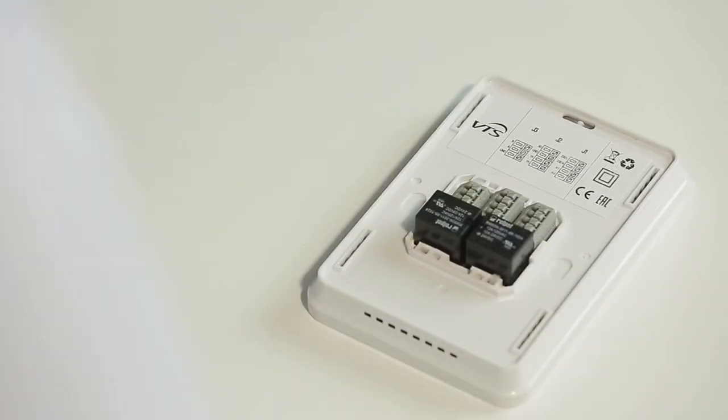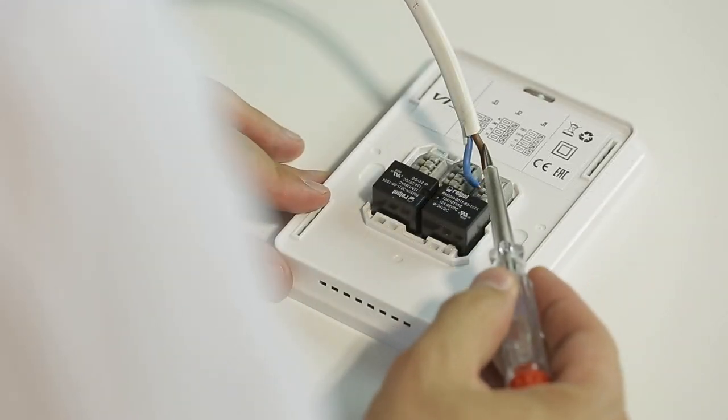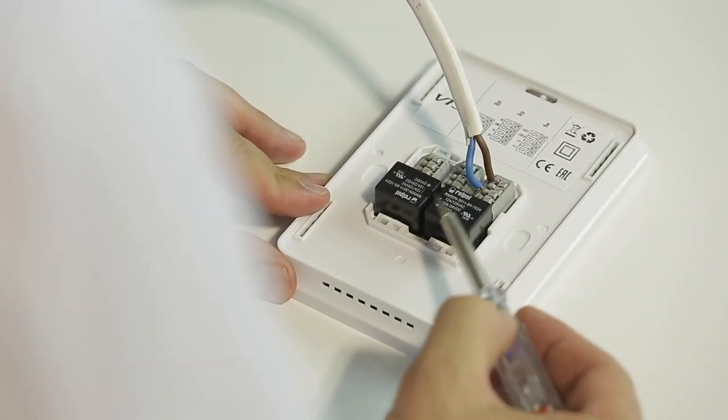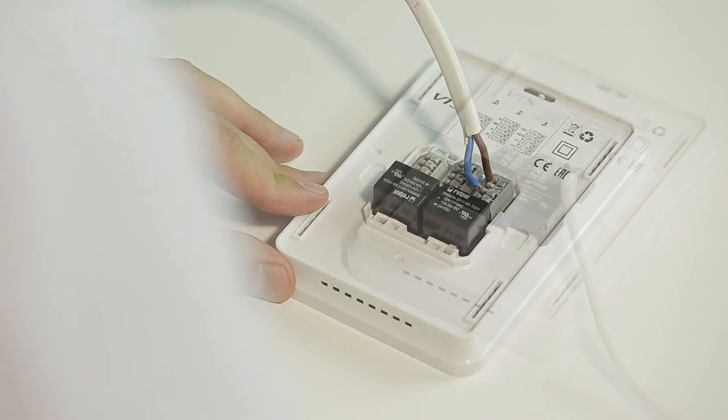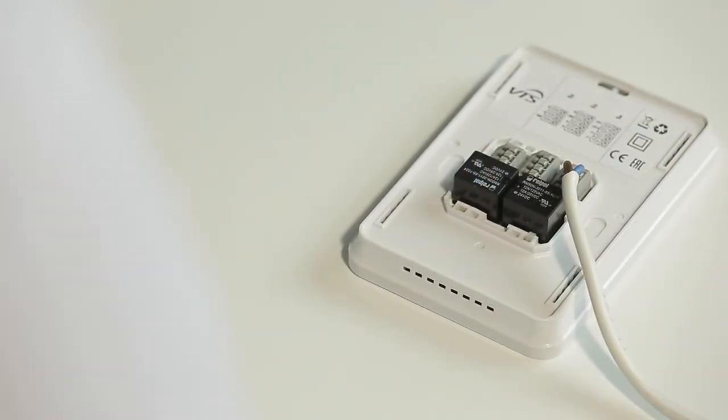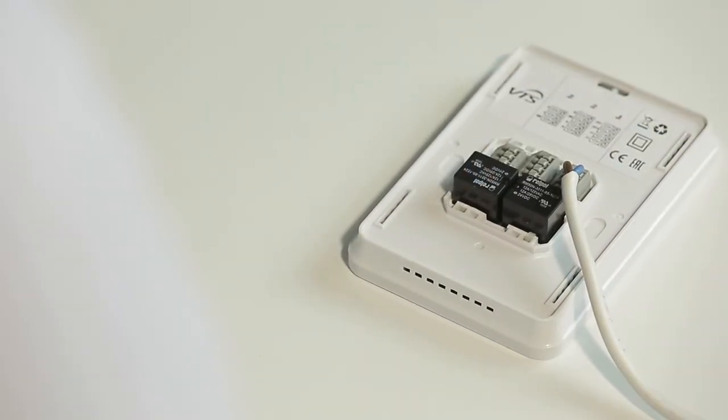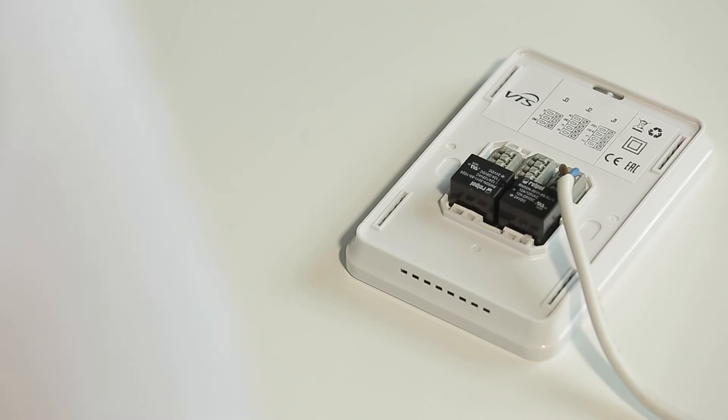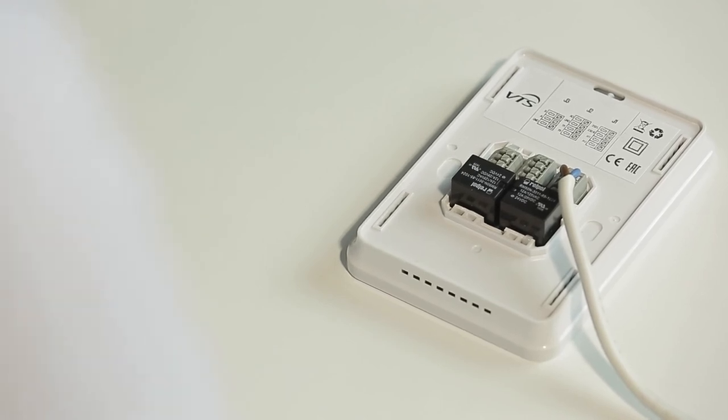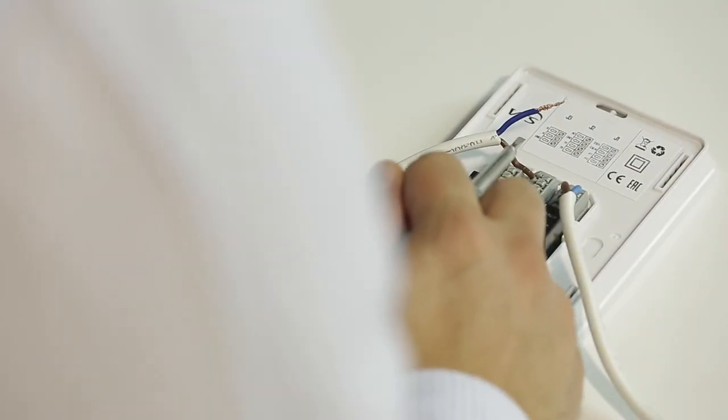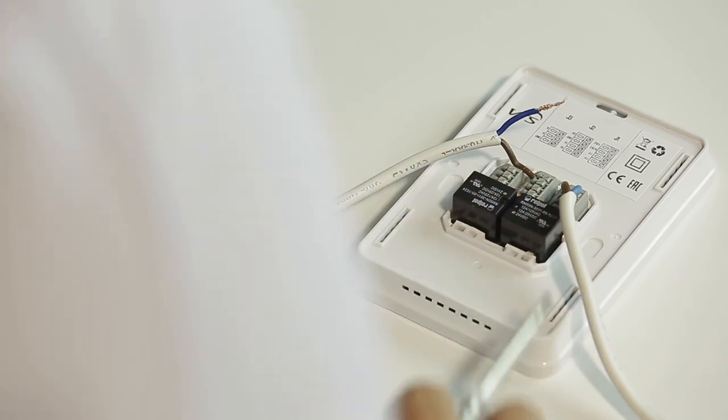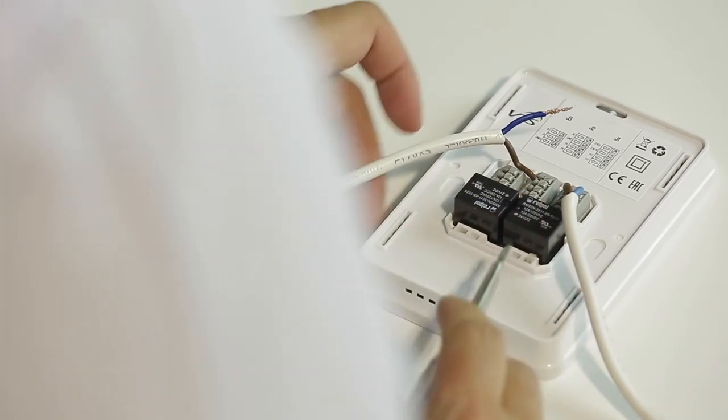Now connect the single phase power supply to the Volcano EC controller. Phase wire, and neutral wire. After connecting the single phase power supply, we proceed to connect a 0-10 volt control signal and its grounding. Control signal 0-10 volt DC and its grounding.